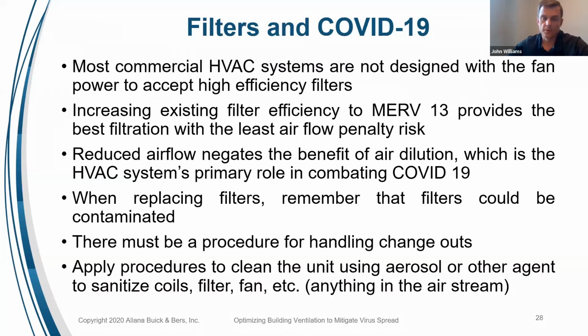When we go to the filters, we typically think of higher MERV rated filters as better. So we go from a MERV 8 to a MERV 13. And to an extent, that is true: with higher MERV ratings, the filters are better. But one of the things we want to talk about today was the concern with increasing the filter ratings and the potential reduction of airflow as a result of not having enough fan horsepower to overcome the filter pressure drop.